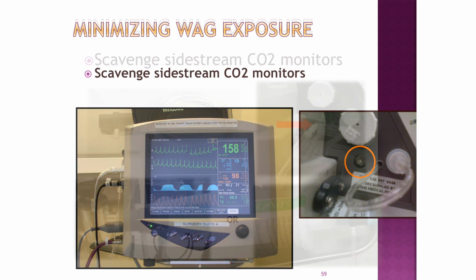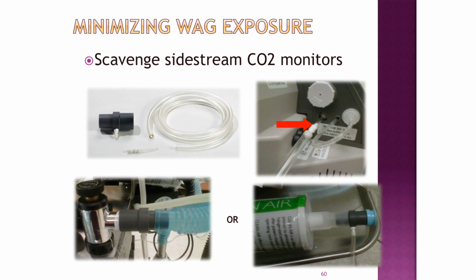So if you're monitoring carbon dioxide, you do have to make sure that you have your scavenging hose hooked up onto that location on the side of the SurgiVet, and that tubing actually does go into the active scavenger interface. You can either put it at the back of the pop-off, as this picture shows, or you can put it right onto the active scavenger interface before your blue scavenger hose fits in.